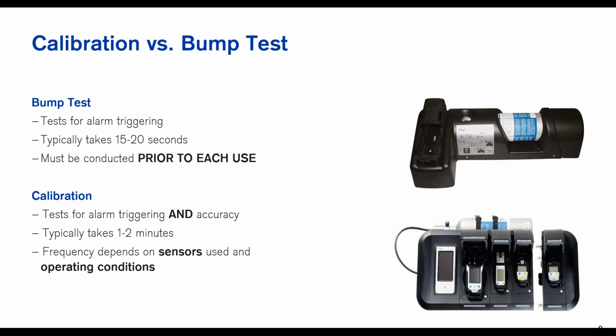If we're exposing it to high concentrations of carbon monoxide or high concentrations of hydrogen cyanide, whatever it is, I'm getting known concentrations on a daily basis, several times a day, then I may have to calibrate that weekly, monthly, whatever it is. You just don't want to over calibrate that because you can decrease the life of your sensor. So you need to base it on what your actual operating conditions are, and then reference your user manual for the particular meter that you have and base it on those sensors.